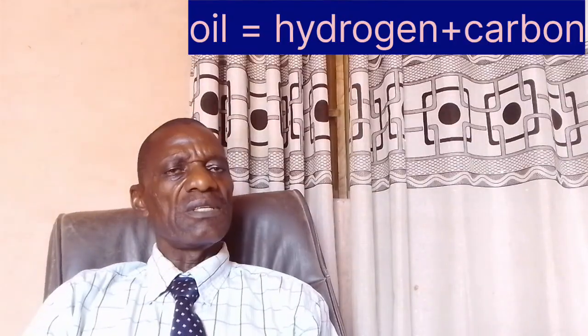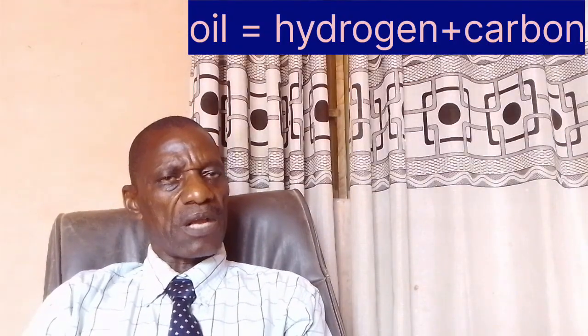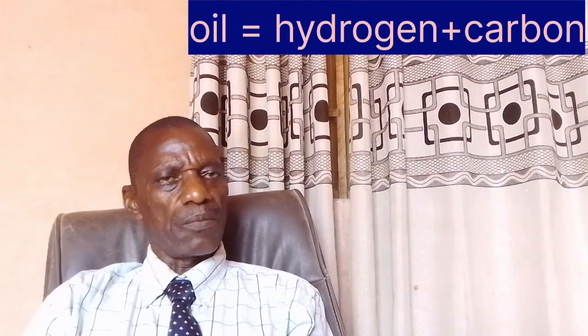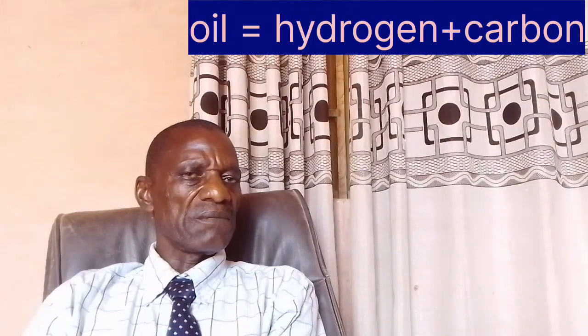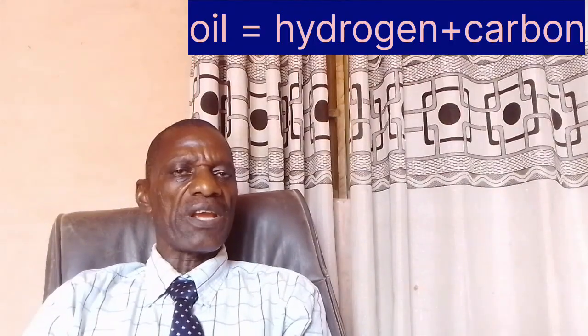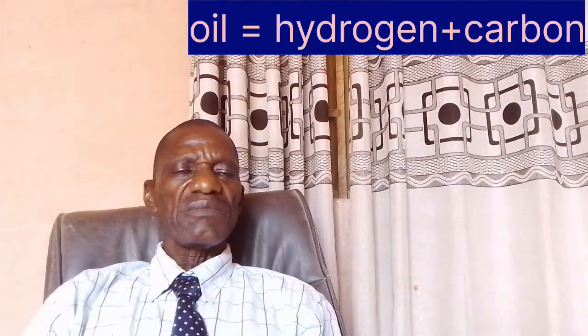The hydrogen is gas, contained in the circuit breaker. Also the carbon, which is a poor conductor, deposits inside the circuit breaker, and in the course of time, when the deposit becomes much, it can cause a short circuit. So that's the disadvantage, and these are the reasons why the oil circuit breaker is being phased out.